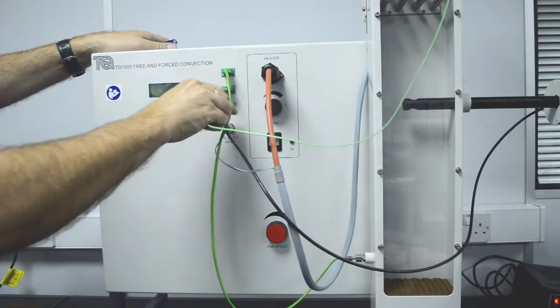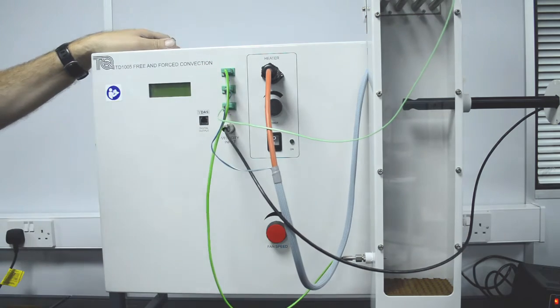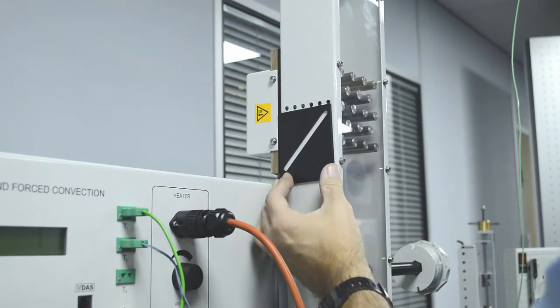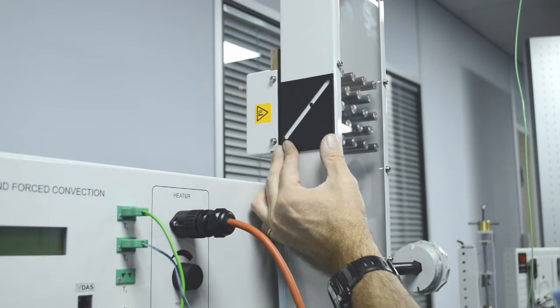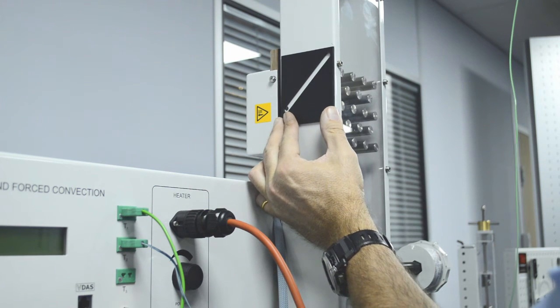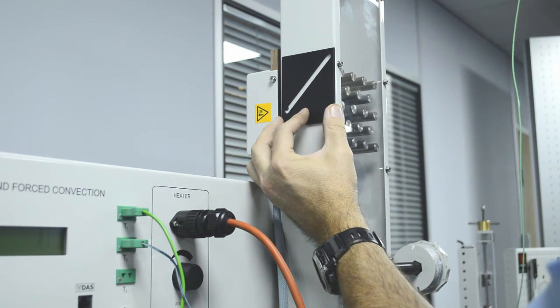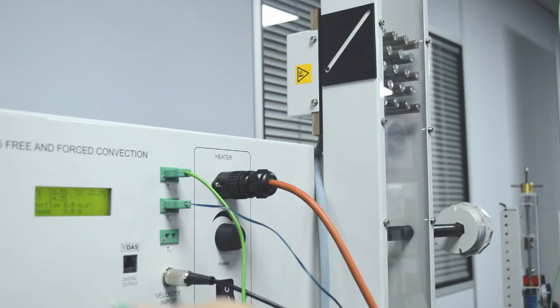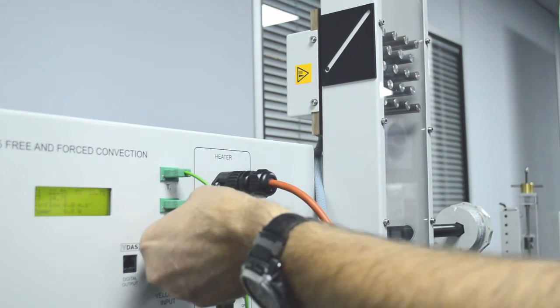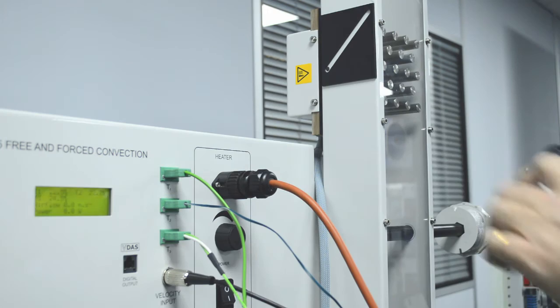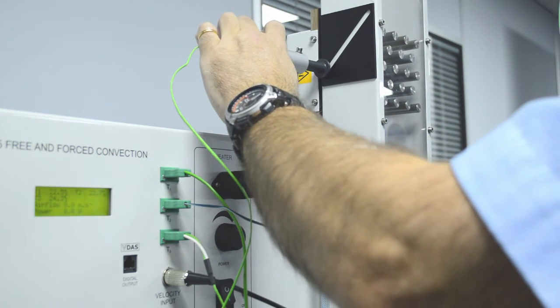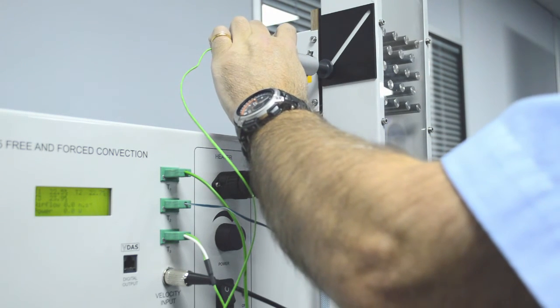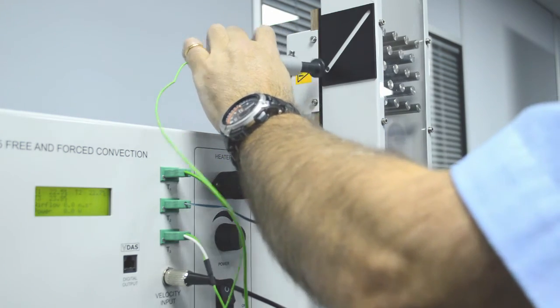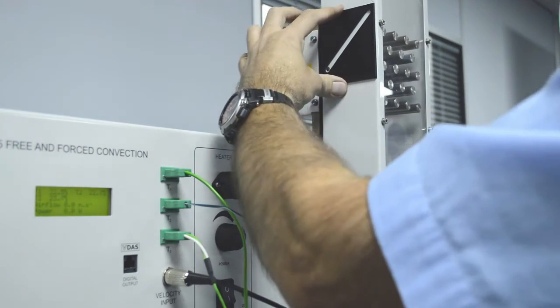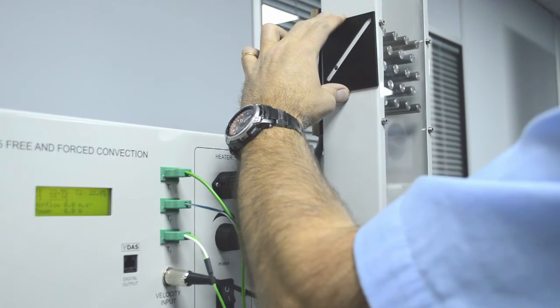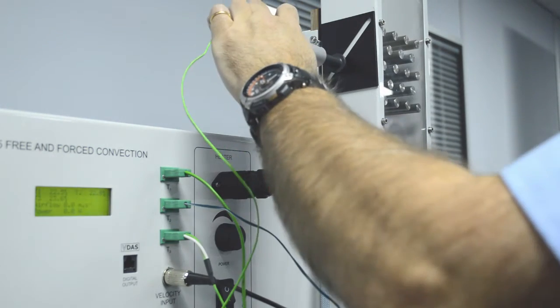The equipment includes a handheld thermocouple probe for heat distribution measurements along the pinned or finned surfaces. The user inserts the probe tip into a selection of 6 equally spaced holes in the side of the duct. The black magnetic cover allows the user to cover the holes completely, so you can only use one hole at a time.